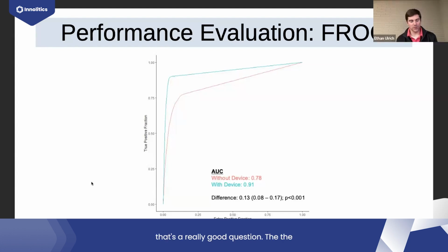So that's neutral, but the device might be completely wrong in some cases. Yeah, that's a really good question, Ilya. The clinical performance assessment is one side of the evaluation. For every submission that I've been a part of, there's also a standalone performance assessment, which is the performance of your device minus the human element. It's actually easier to perform. You just take the output of your device, compare it to your ground truth, like a dice score for the lesion segmentations, and report that. That would detect if my device is way off and my readers are just really good.